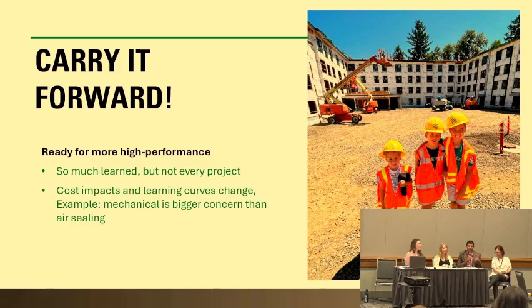So this building had cooling in the ERV, and there are some challenges and limitations there. One is there's not a lot of airflow, so you're limited by how much air is being moved, and that limits how much cooling you can do. The other thing is the temperature of that air. Unless you insulate the ductwork, you're limited to something like a 60-degree supply air temperature, so that also limits the amount of cooling you can do. So with central ventilation, it is not a comfort cooling solution at all. It'll improve comfort, but it won't get you there.